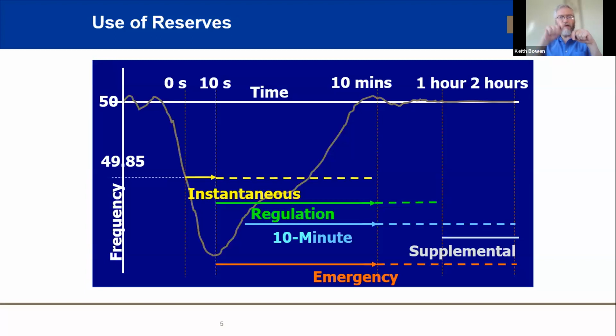What we use to control that movement of the frequency is regulation, or the secondary reserve, which is really automated generator control. Regulating control really is there to send out pulses from the central system operator system to various generators to get them to back up or back off, depending on where we are on the frequency. So the frequency curve can go above or below 50, and you're trying to manage it within a certain bound. That regulation control, you also try and spread it out amongst a large number of generators, so that you're not relying on 3 or 4 generators to provide that regulating capability, and then find they're not there when you need them, or you have a limited capability because one of them has tripped.